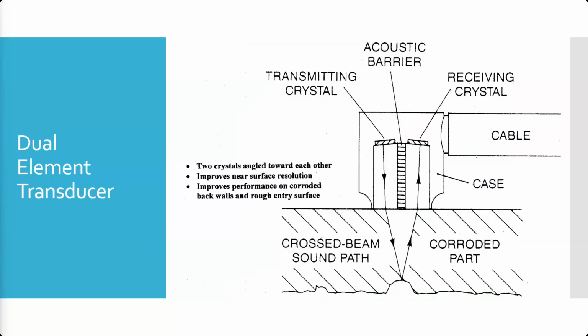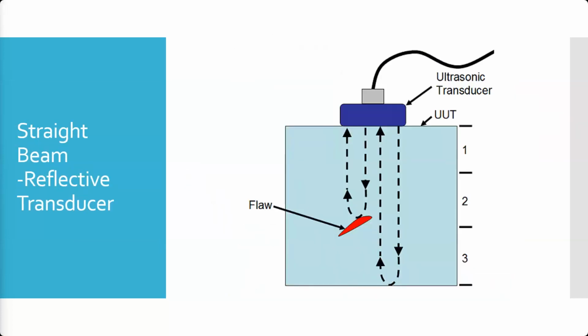Here again is that dual element transducer. There are two advantages here. We can have separate crystals that are tuned to their purpose for transmitting and receiving. The other thing is, when you do a pulse echo and the sound goes down and back up again, if your pulses overlap, there is the possibility that the pulse traveling down can interfere with the sound waves traveling back up. So there is a certain amount of interference possible here. In most cases, it's not too big of a deal.